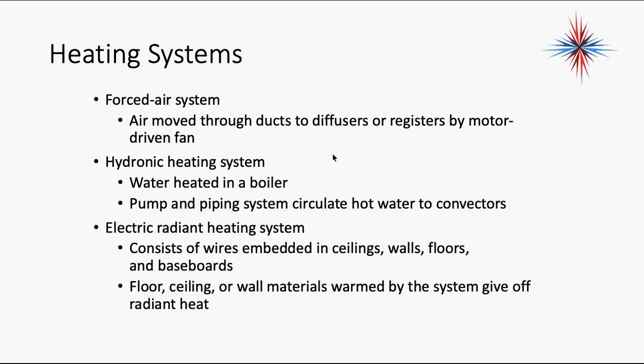With hydronic heating we also have radiant heating, where you don't see any registers or diffusers — it actually warms the floor. Electric radiant heating systems consist of wires embedded in ceilings, walls, and floors or baseboards; the floor, ceiling, or wall material is warmed by those wires and gives off radiant heat. Hot water radiant systems are extremely efficient and comfortable. Electric radiant was popular back in the 70s and 80s when power was inexpensive, but it costs more today.